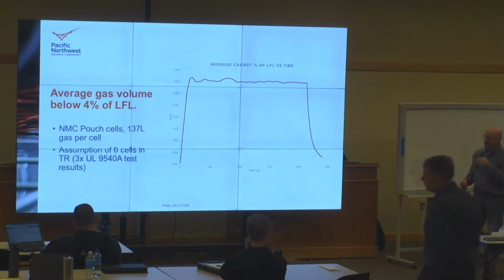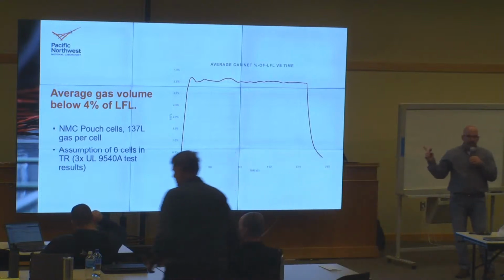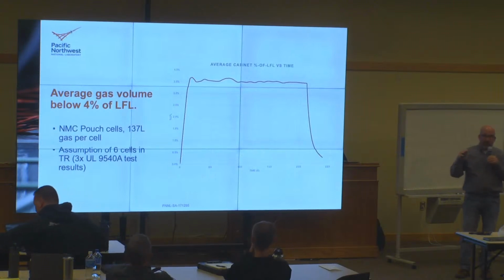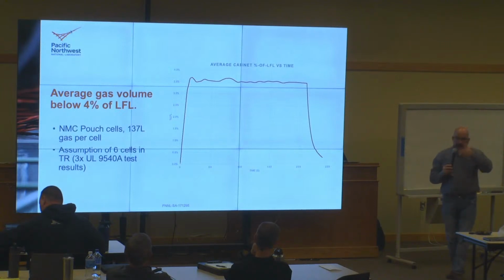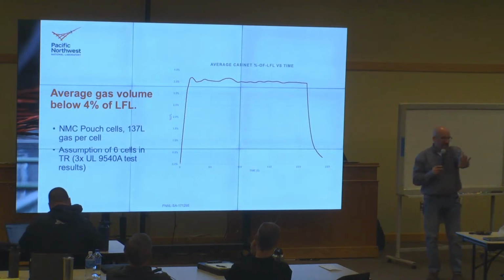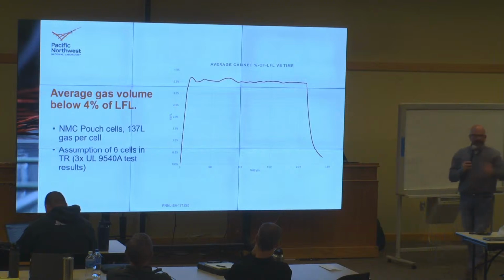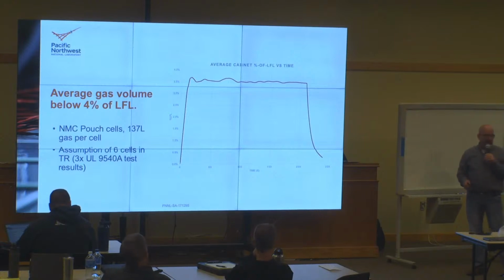We expect to see a lot more systems consider this. We've seen RFPs for projects in the hundreds of megawatts by utilities asking for automatic doors on their systems. Now, what that will do, though, is if you have a fire, it becomes visible to the next cabinet, so manufacturers need to know the heat flux and design their insulation and distancing consistent with that data. UL will do a lot more testing of these systems, but it will change the test, because the current test does not require ignition of the gases, and that's a big gap in a lot of people's minds.